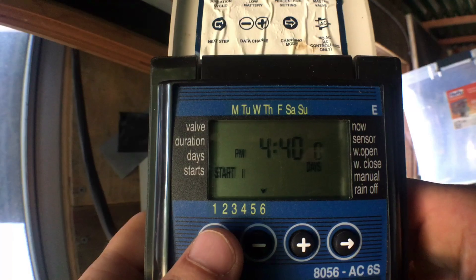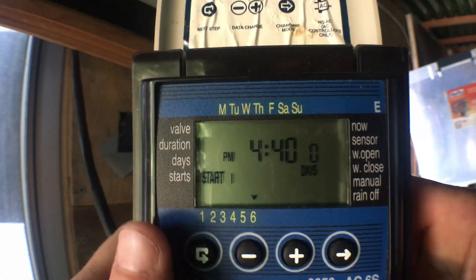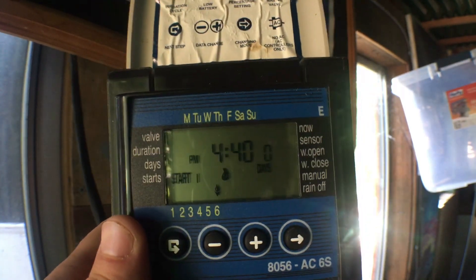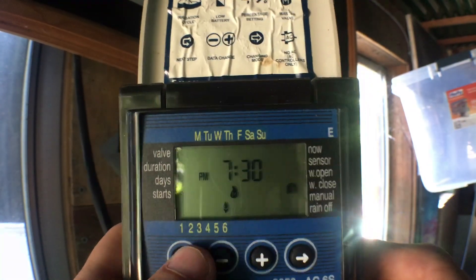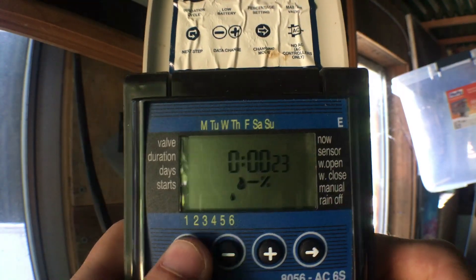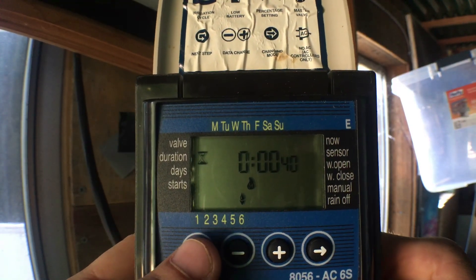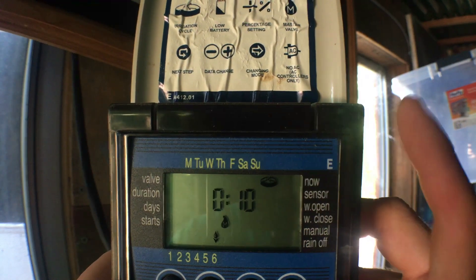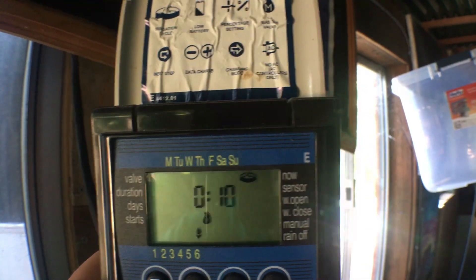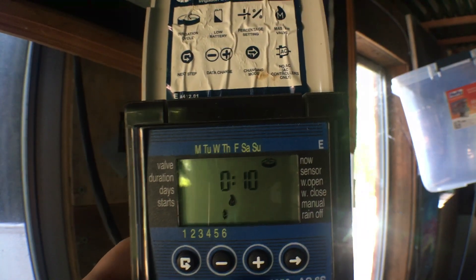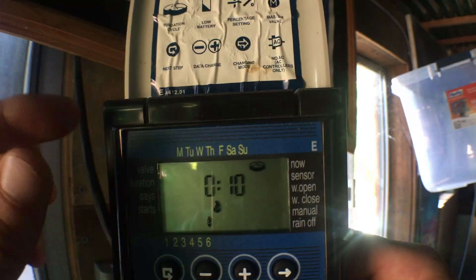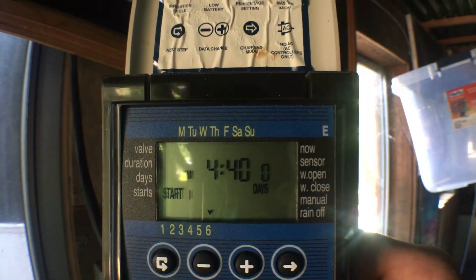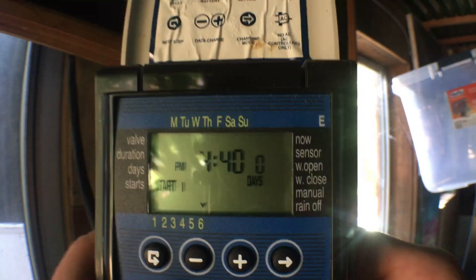Now I'm on start time. This one is not important because I'm in cyclic irrigation mode. When you're in cyclic mode, that little circular arrow icon basically says every ten minutes for 40 seconds, run this cycle between a beginning and end time that we'll set later. So your start times aren't really important here because you're not setting an exact daily start time on a specific day of the week — you're doing it every single day.